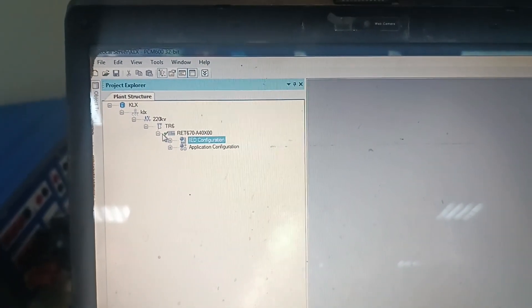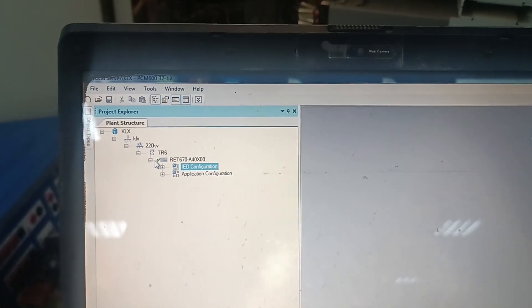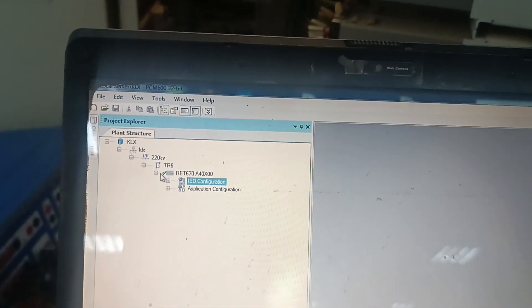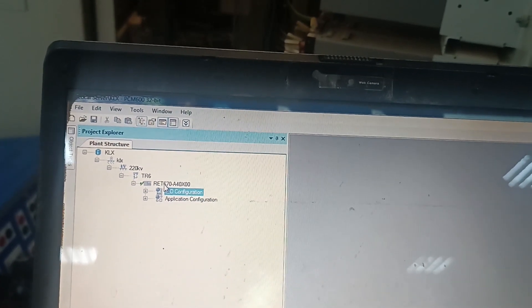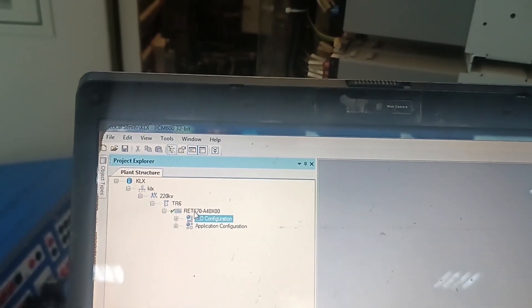This is the required setting to establish the communication between IED and RTU. There is an additional configuration in order to transmit these signals from RET670 to RTU, and this setting will be done using the configuration software PCM600. We will see how to add the event block and then how to connect the signal with this event block in order to be able to send this signal to RTU.